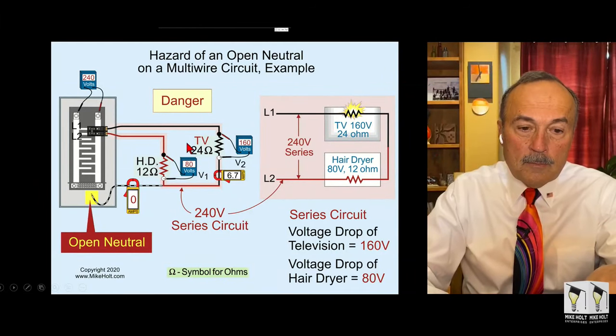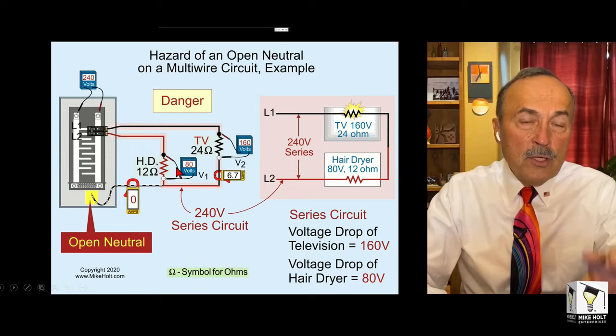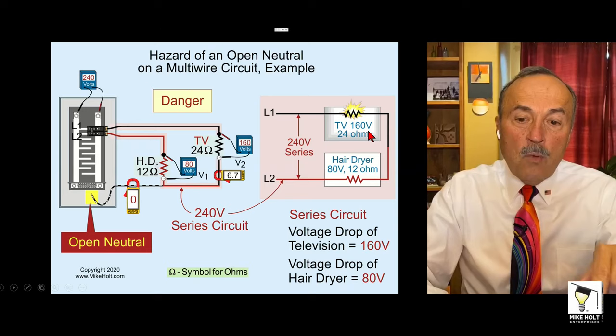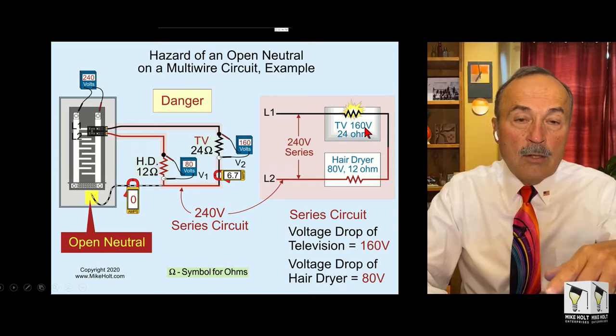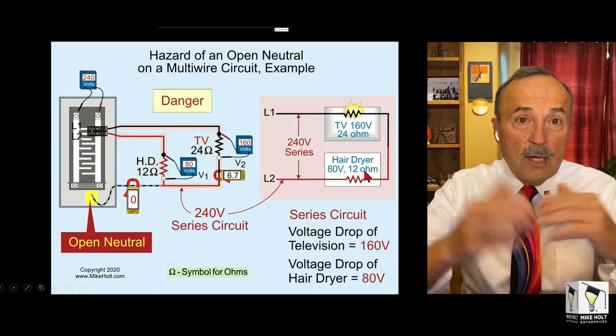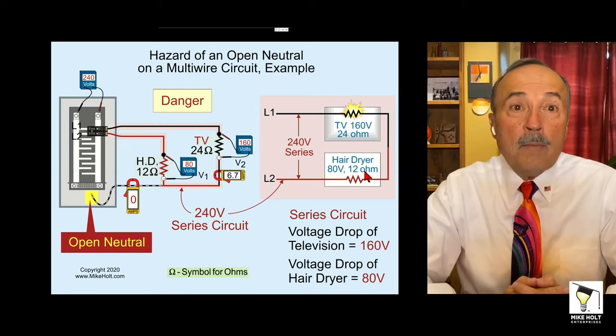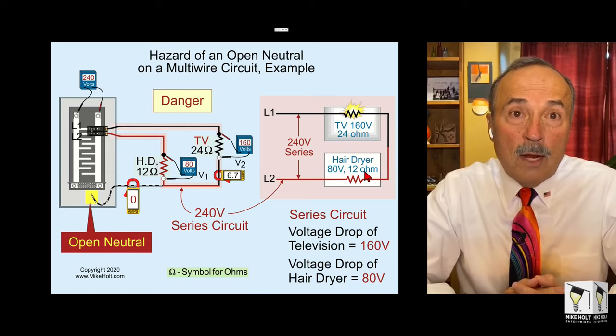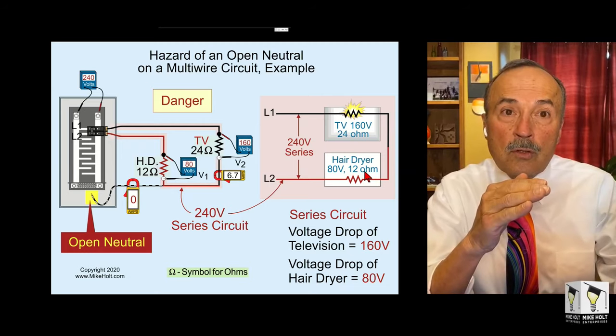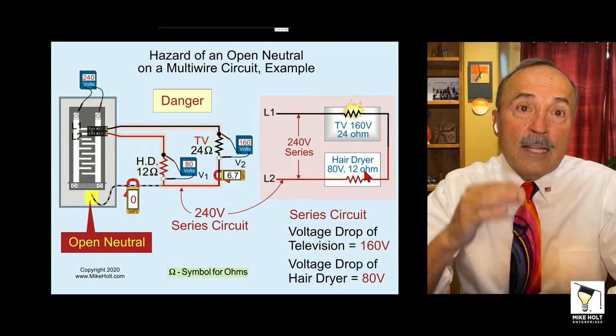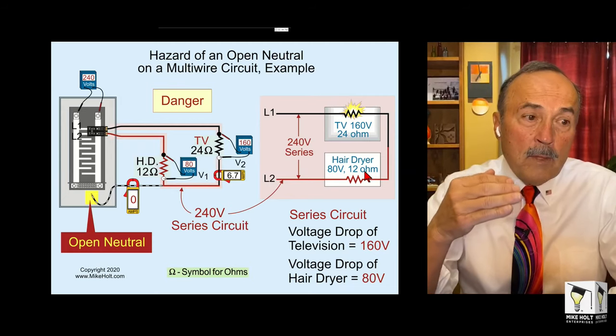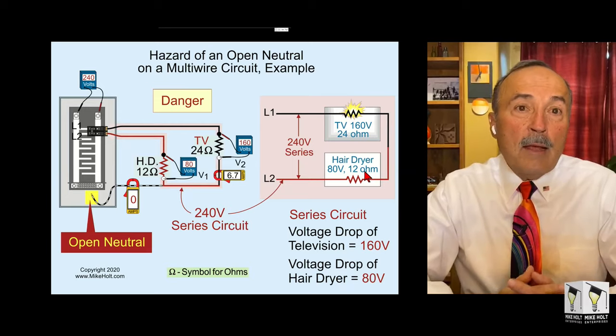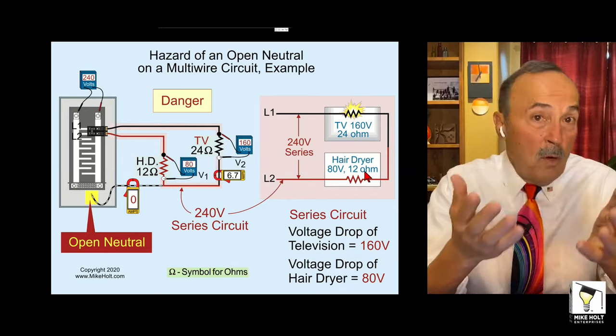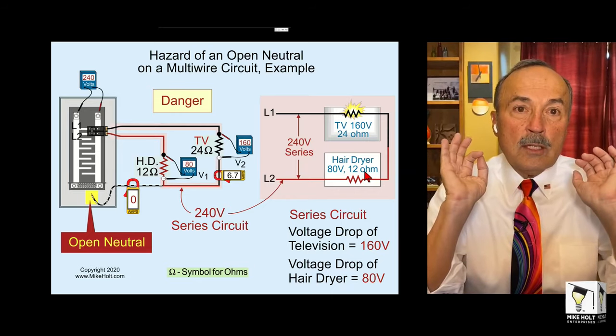Okay. I don't know for a fact, but I believe it's probably true. You have to realize something. Let's go back over here. On this multi-wire branch circuit, this could happen on a utility. If the utility loses their neutral, you could end up having one line up in your house, okay, 160 volts, and the other line could be 80 volts or any combination thereof. If you had AFCI breakers on that two-pole, on that multi-wire branch circuit, or any one circuit, and the utility loses the neutral, the voltage goes so high that it's an overvoltage condition, and apparently the electronic protection device, I don't know if this is true or not, they self-protect themselves. And when they see over supposedly 160 volts, then they just disconnect off of the circuit, which makes total sense.